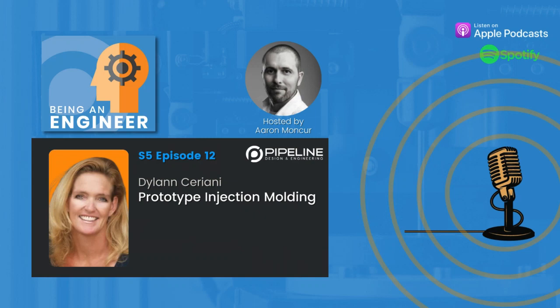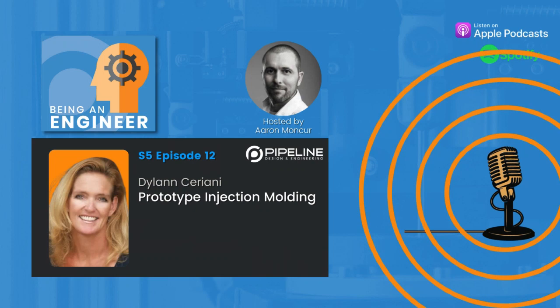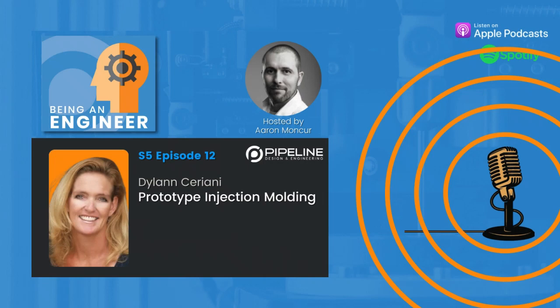As far as engineering goes, when you are doing a medical device and you are required to be under design control, it's a lot of what you do. You have to do design and development plans. You have to have a design input. You have to have a design output that matches. So you show, okay, this is what I said it was going to do. And here's the proof that this is what I said it was going to do.